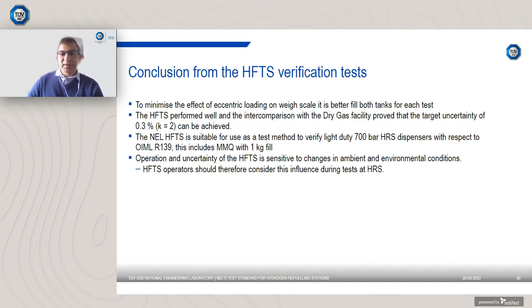So what are the conclusions that we can make from the verification test? One is that in order to minimize the uncertainty in the weight measurement, it's best to decrease the eccentric loading on the weighing scale, and therefore it is better to operate the rig with both tanks filled. The test rig, or the hydrogen field standard, performed well, and in the comparison with the dry gas facility proved that the target uncertainty of 0.3% could be achieved.